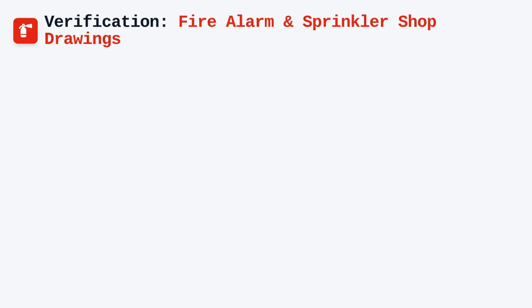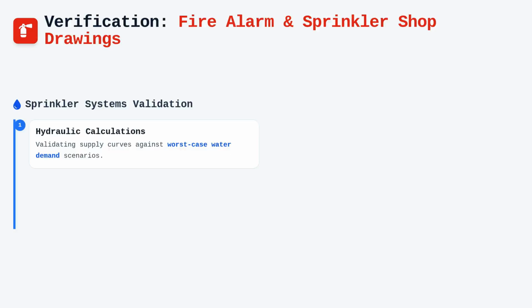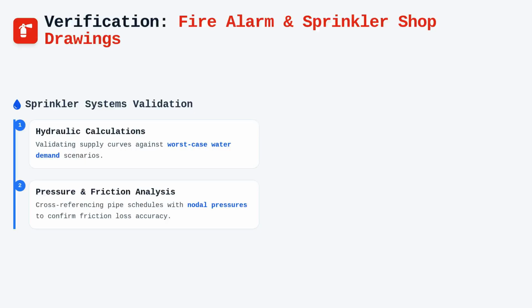Moving into fire alarm and sprinkler shop drawings, the verification shifts toward technical capacity and hardware compatibility. For sprinkler systems, we review hydraulic calculations by validating that the provided supply curves are not only accurate, but represent the worst-case water demand scenarios for the building. This involves checking pipe schedule cross-references against the calculated nodal pressures to ensure the friction losses were accounted for correctly in the design.